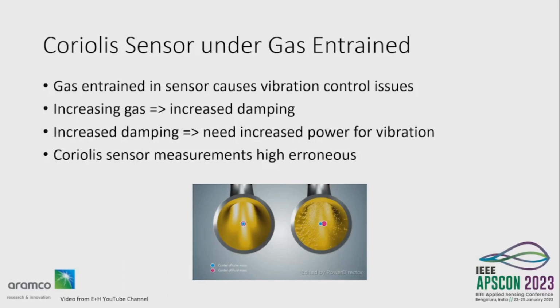So what is the effect of gas entrainment in such flow sensors? These meters are designed to measure very pure fluids, but when small amounts of gas are entrained, it causes a big problem with vibration control of the vibration tubes, because increasing amounts of gas means increasing damping on the vibration, which means you need to put in more power. There's obviously a limit to how much power you can put into vibrating these tubes, because safe operation requires a limited amount of energy. The other problem is that the measurements from the meter become highly erroneous, because the density and mass flow readings are now out of spec.